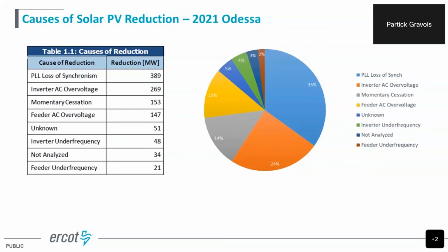The biggest was the phase lock loop loss of synchronism, 389. Then we had overvoltage, momentary cessation. All of these were things that were typically seen in other events that NERC had already analyzed, like the Blue Cut Fire in California and a couple other events as well. Some of them were really particular, like a feeder under frequency breaker trip, things of that nature.